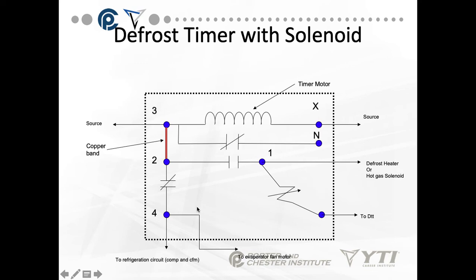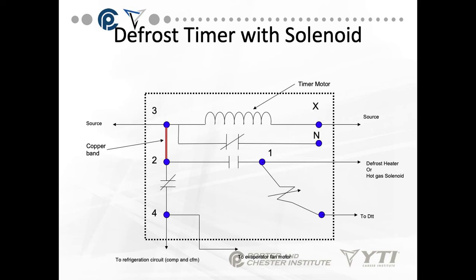This is a different type of defrost timer. You'll notice X is the other source. We have neutral and we have X, but on this case the N terminal is actually a line-powered terminal. So be careful when you look at these clocks — you do have to look at the diagrams, because different manufacturers use different pin designations.